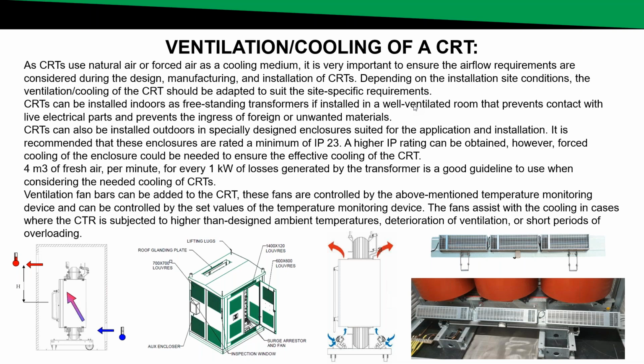Due to the fact that cast resin transformers use natural air and sometimes forced air as a cooling medium instead of oil, it is very important to ensure the airflow requirements are considered during the design, manufacture, and installation. Depending on the site installation conditions, the ventilation cooling of the transformer should be adapted to suit the site-specific requirements. There are generally two types of installations for cast resin transformers. As a cast resin transformer is manufactured as an IP00, it can be installed indoors as a freestanding transformer.